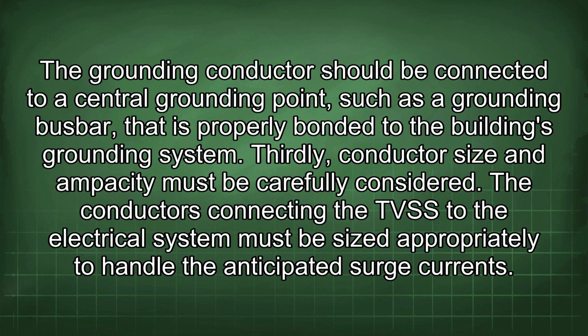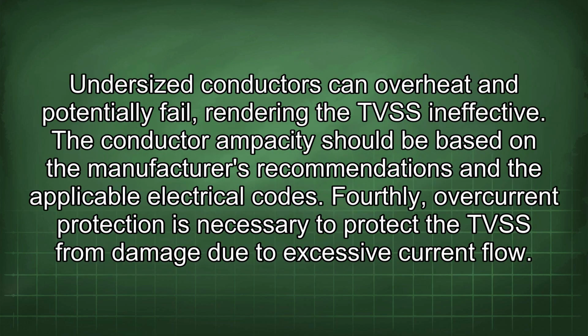Thirdly, conductor size and ampacity must be carefully considered. The conductors connecting the TVSS to the electrical system must be sized appropriately to handle the anticipated surge currents. Undersized conductors can overheat and potentially fail, rendering the TVSS ineffective. The conductor ampacity should be based on the manufacturer's recommendations and the applicable electrical codes.